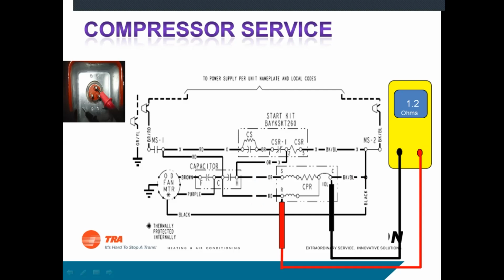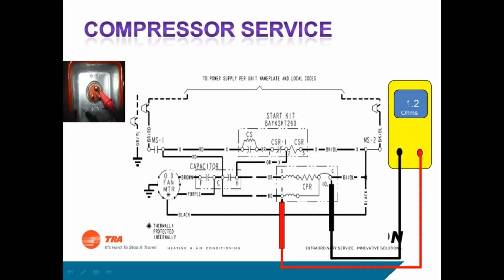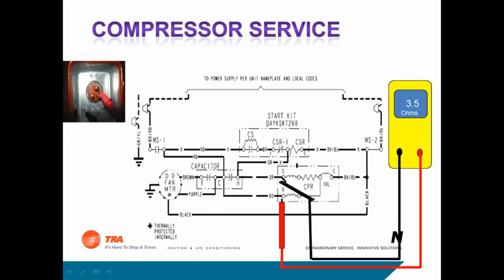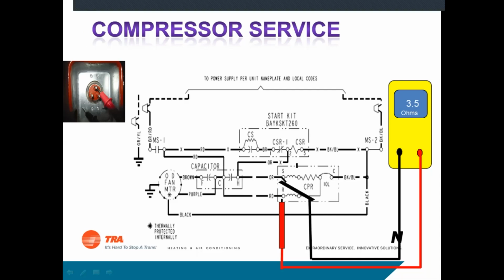So if anybody wants to write these down and do the math, you're welcome to. But if I take an ohm value reading between common and run and I see 1.2 ohms, that probably looks okay. That's a good ohm value for a run winding. So if I take an ohm value between common and start, I might see 2.3 ohms. Again, that's probably a fairly comparable reading that you'll see in the field. And if I go between run and start, all we're doing between run and start is adding the value of these two windings together, and that should equal the total of the first two, which in this case it does.